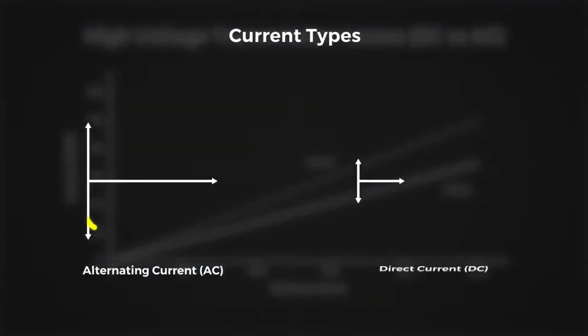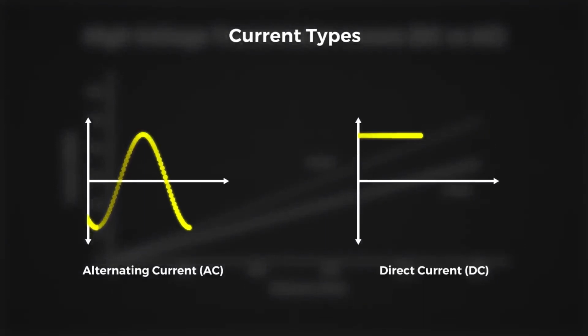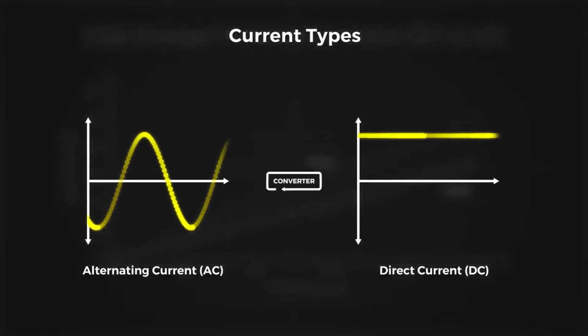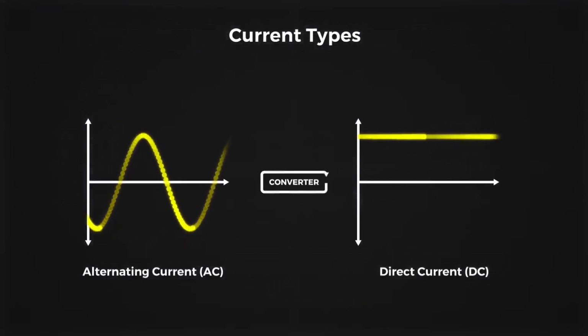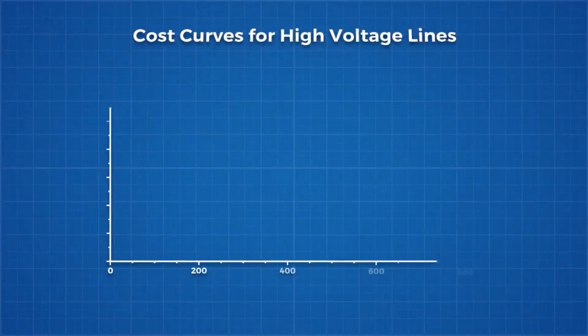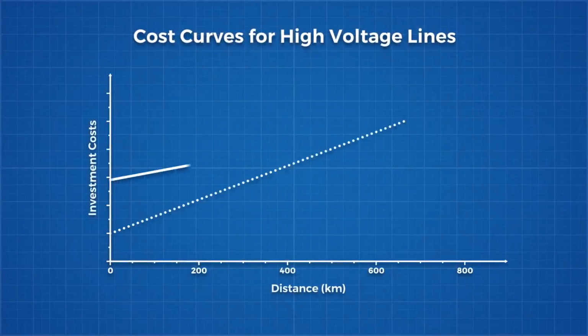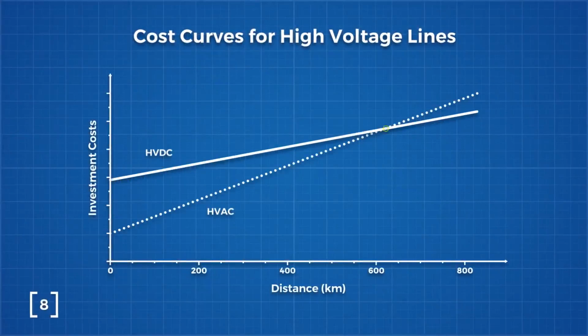However, in order to convert our regional AC grid power to DC for these long-distance transmission cables, we need expensive transformers and converters. If we instead plot cost versus distance, counting in this infrastructure, it would look something like this. And we can see that the DC and AC lines cross each other around the 500 to 800 kilometer mark. This is the break-even point, where DC becomes more cost-effective.